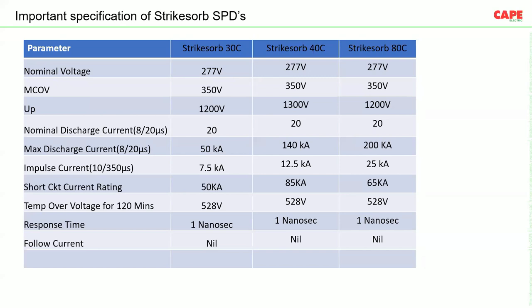Response time, one of the most important parameters with respect to an SPD. All the busbar mounted SPDs have a response time of 1 nanosecond. And there is no chance of follow current in a Strikesorb series SPD, a busbar mounted SPD, because it's a MOV based SPD.